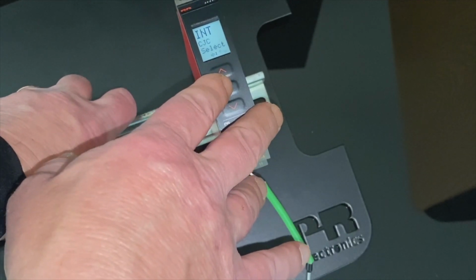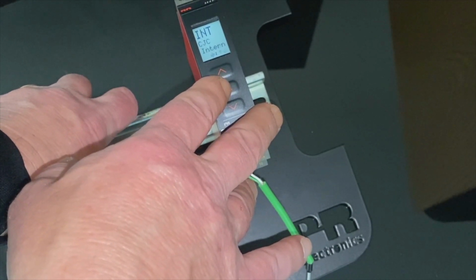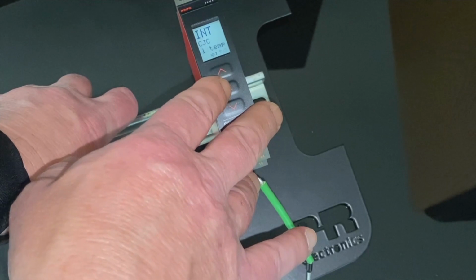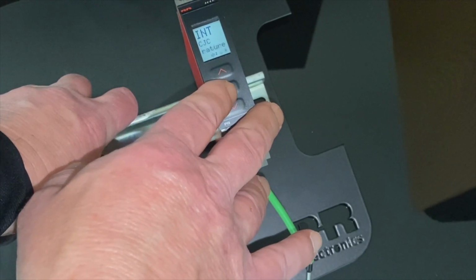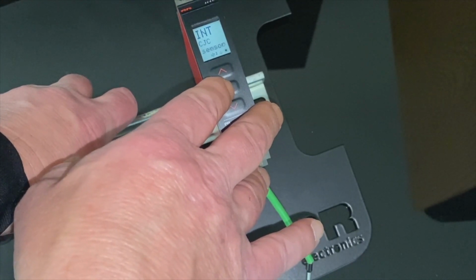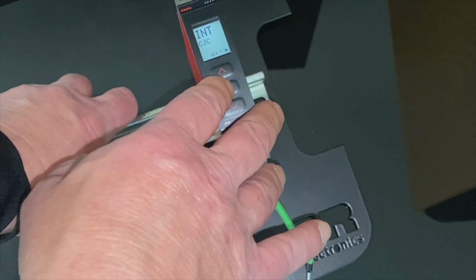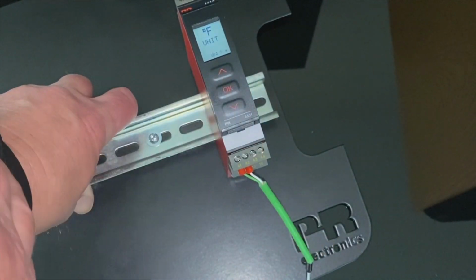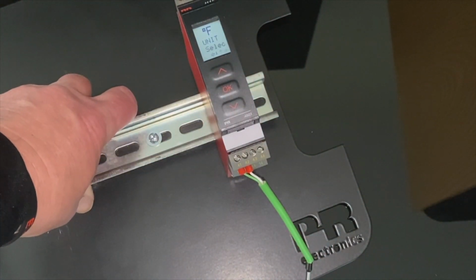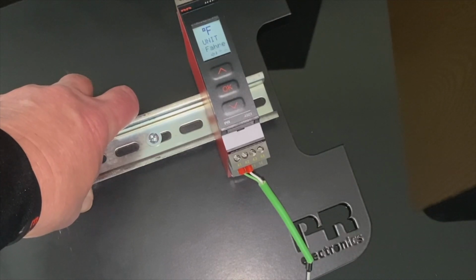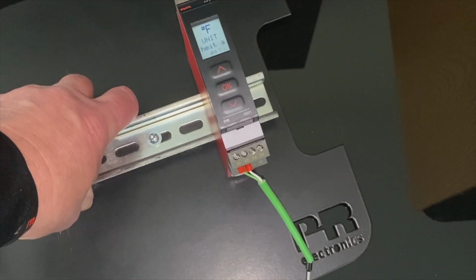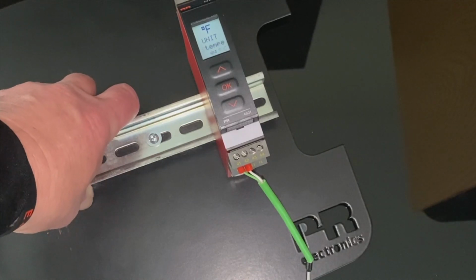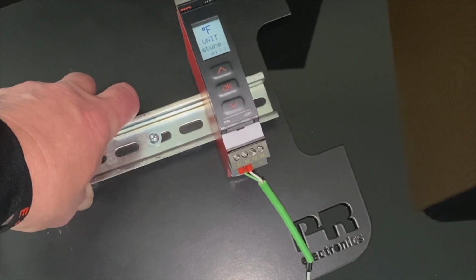The 4116 does have internal cold junction compensation, but we can also work with external. Just know that you need a different terminal block in order to do that, which is a very inexpensive method or a terminal price. So here it's asking you what type of engineering units you want to work with. Because we're talking about temperature here, our choices are limited to C and F.